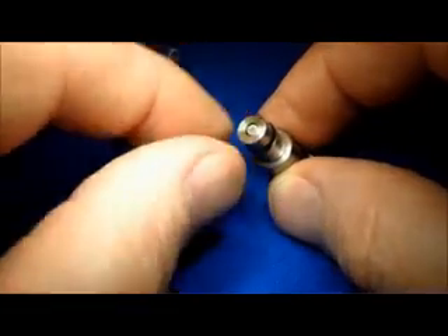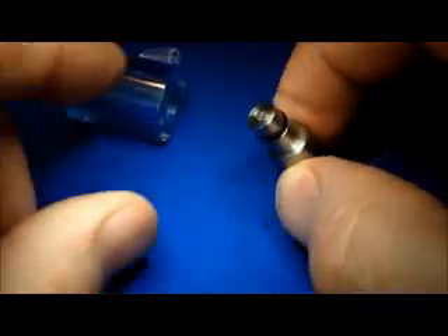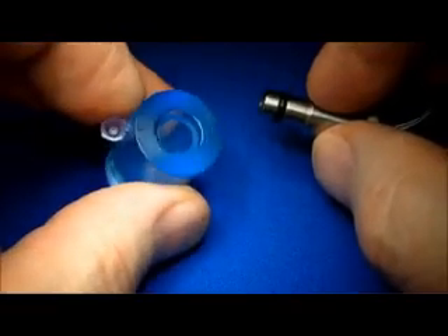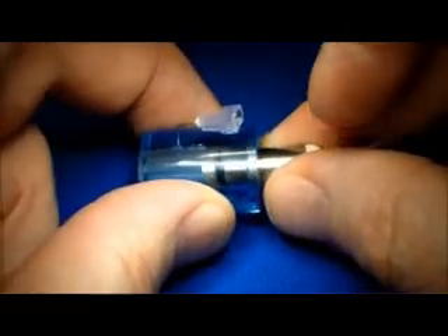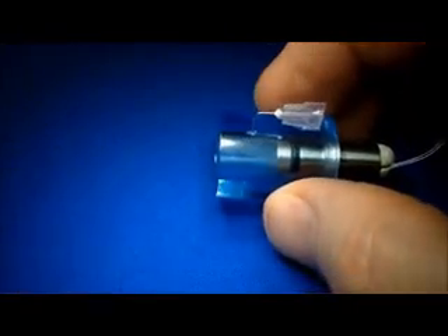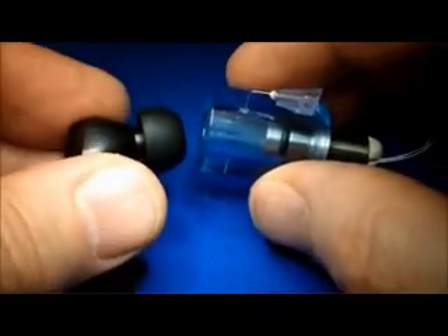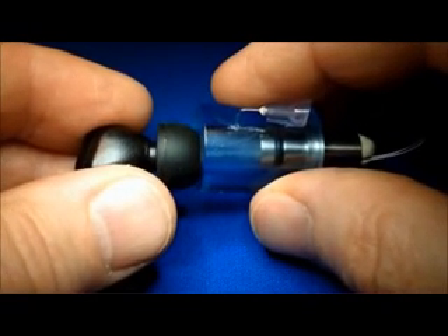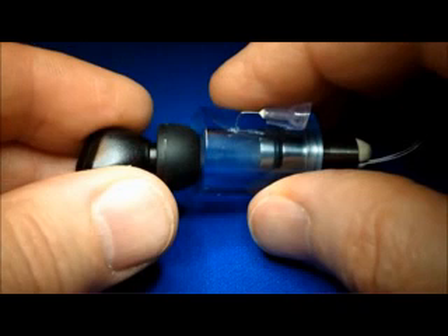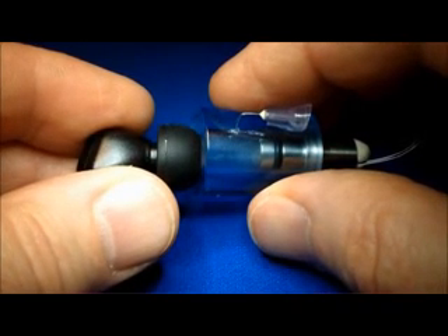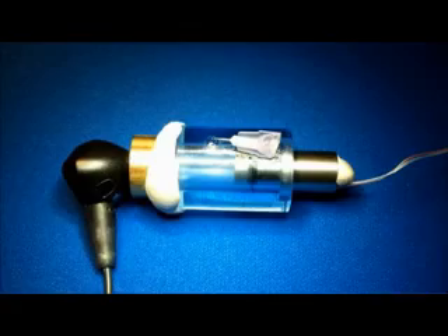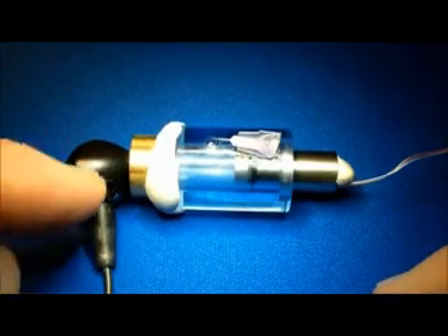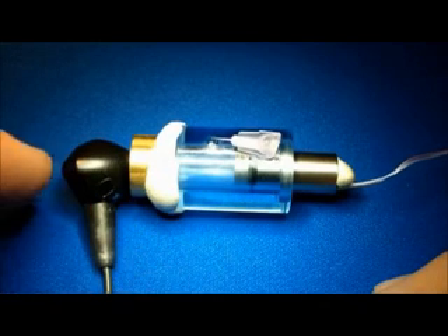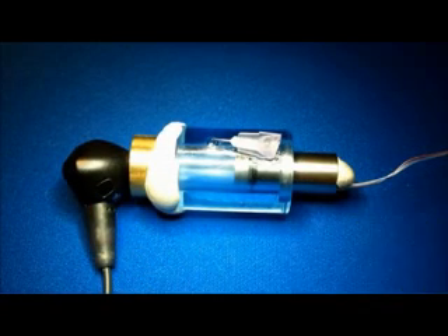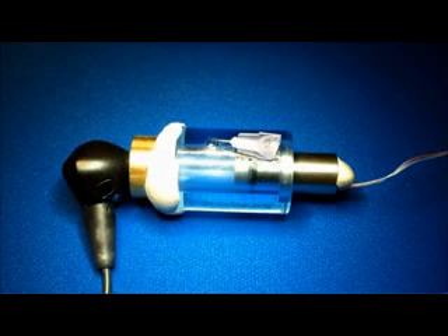To give you a bit more insight, that small microphone has been placed in this holder, and this device I have here in my left hand could represent the trapped volume. So the microphone would be in the trapped volume, and then the earpiece would fit over the end and seal tightly. So the volume you see between these two would represent the trapped volume in the ear canal. Now, for demonstration purposes, I've added a small ring here so that I can connect the receiver to this trapped volume and talk a bit about how the Stapedius reflex measurement is made.